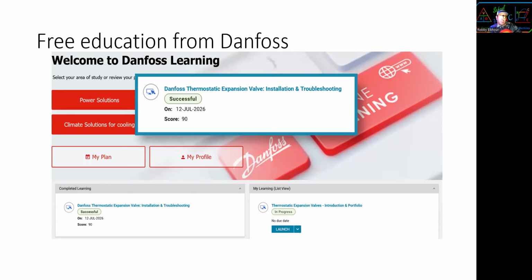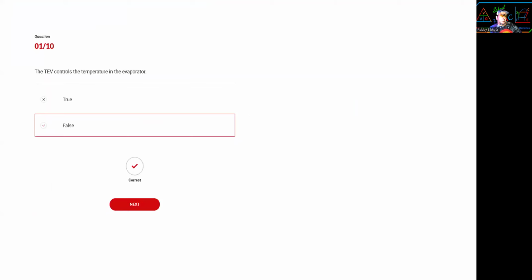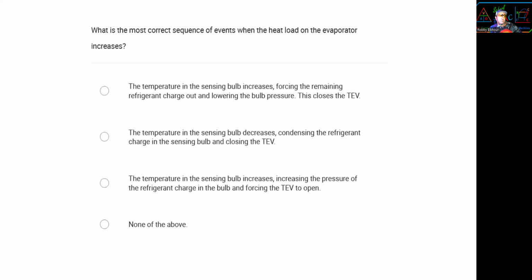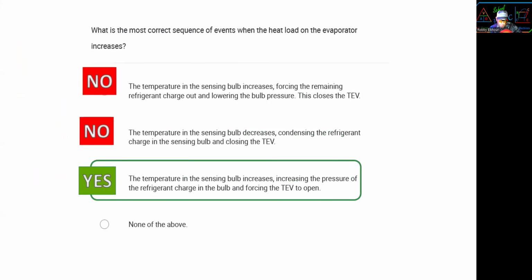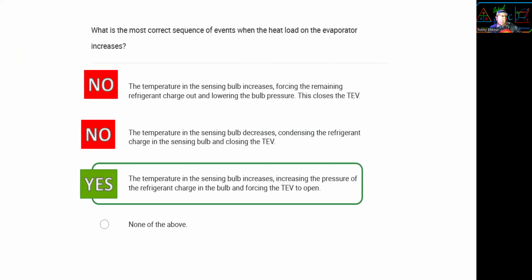Welcome to Danfoss Learning. Question 1. The TXV controls the temperature of the evaporator, and it's false. It controls the pressure. What is the most correct sequence of events? The temperature of the sensor bulb increases, pressure of the refrigerant charged in the bulb increases, forcing the TXV to open. Correct.